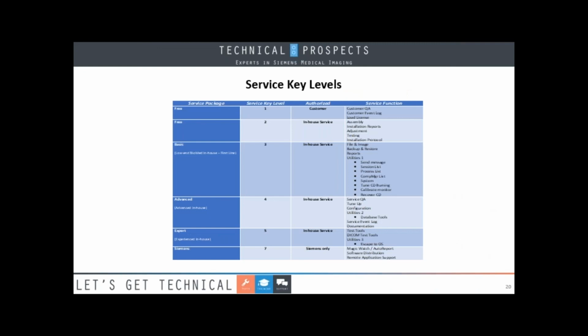And if you get one, here's what you get. And this is basically a level 4, okay? But if you need to go into test tools, which is 5, you'll need to get a level 5. You can call them, and if you can justify that level 5 service key, you'll get a higher level for a few days. And I hate to say it, but it does depend upon what you're doing and the mood of the person handing out the keys. I've had the same person say no and yes to the same thing.